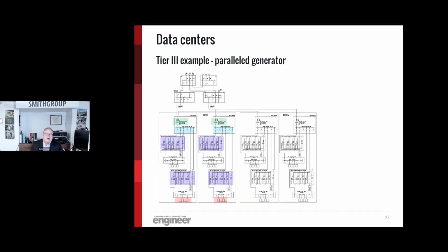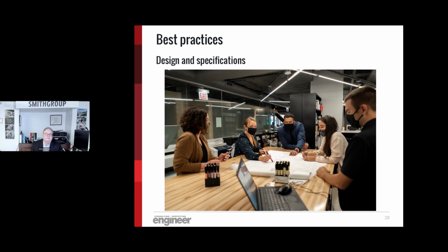Okay, Zach mentioned parallel generators. In some applications, particularly high performance computing with a high density, you can parallel generators. This allows you more capacity and allows you to simplify operations without having multiple smaller generators. So let's, Zach and I, get into best practices.